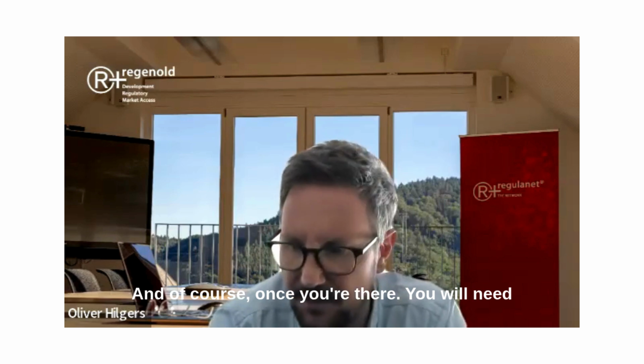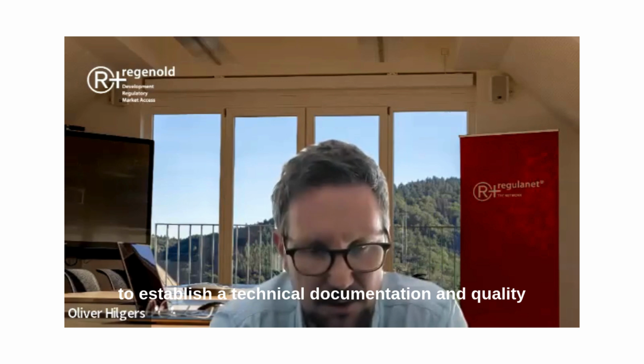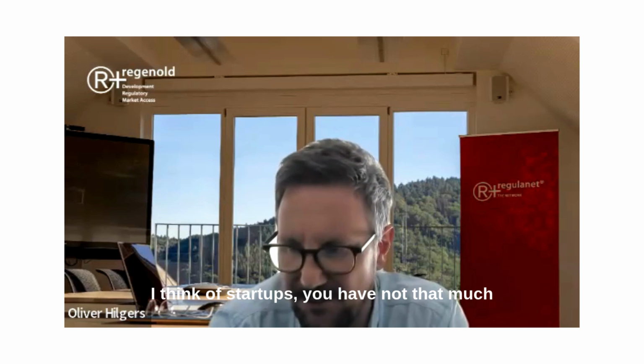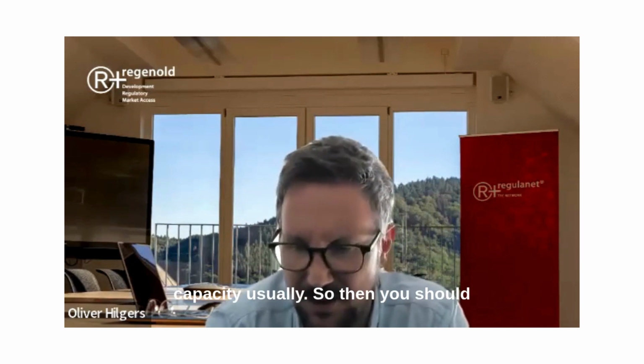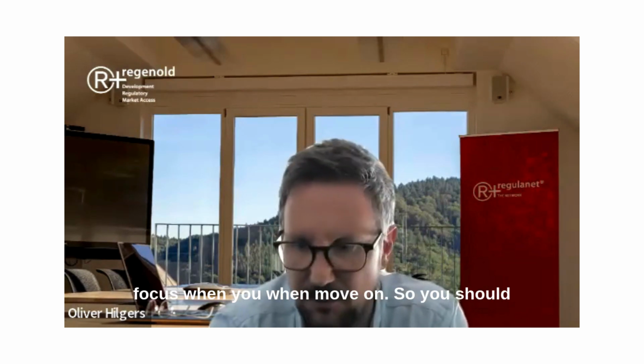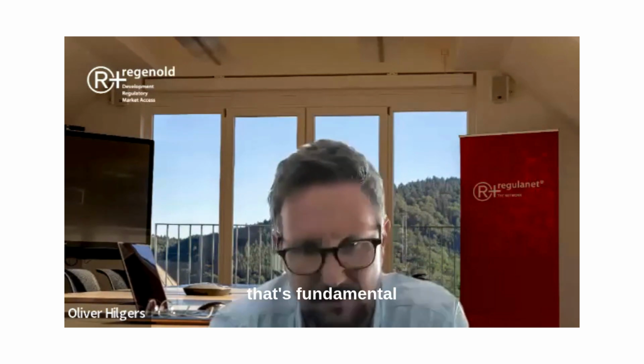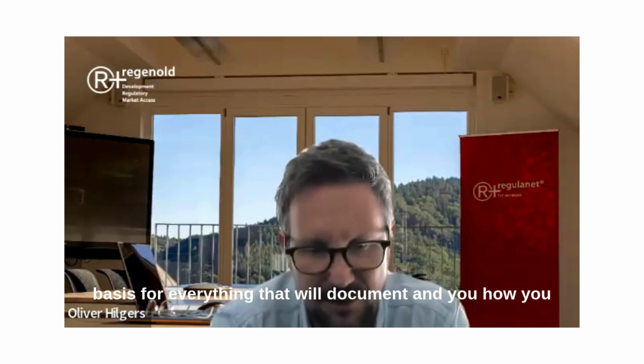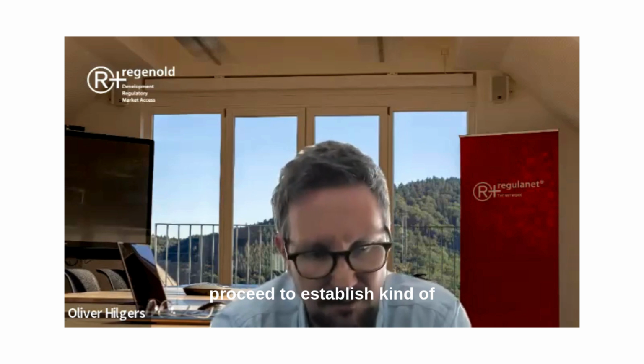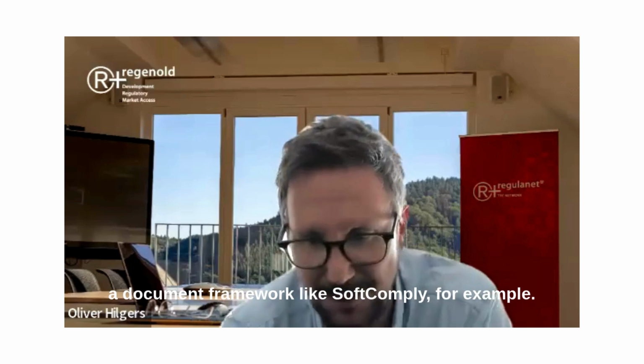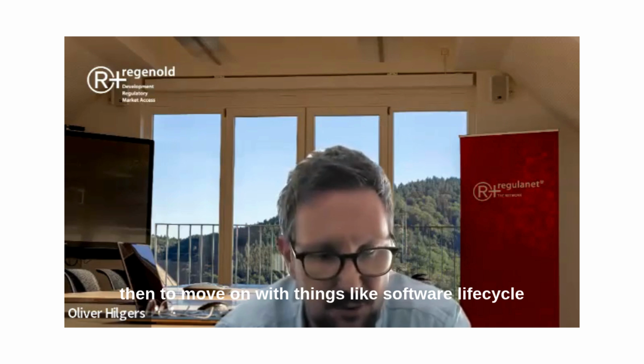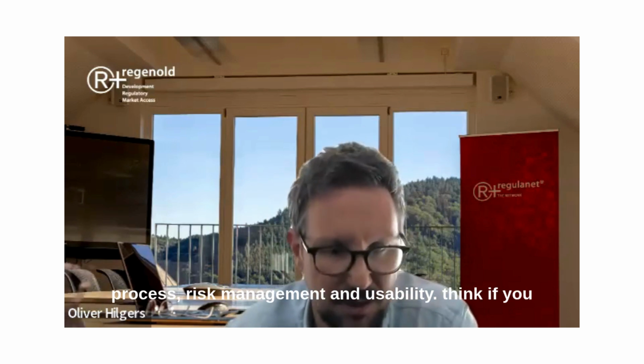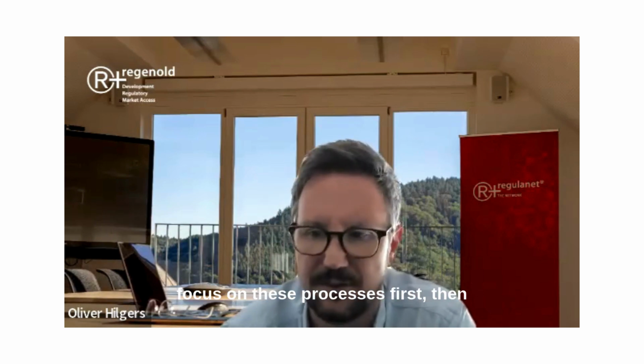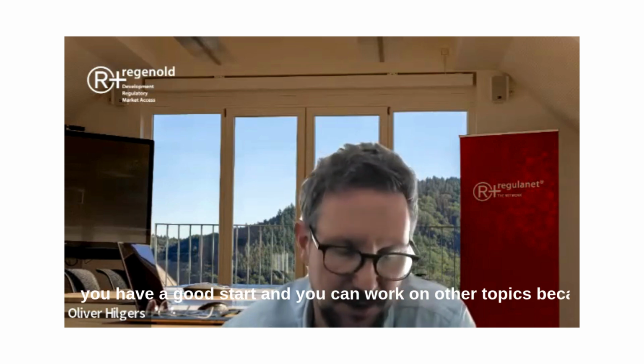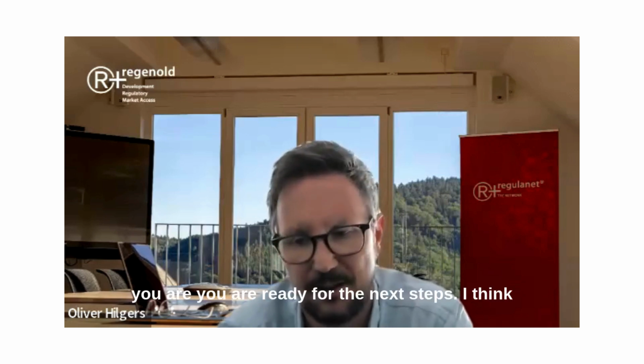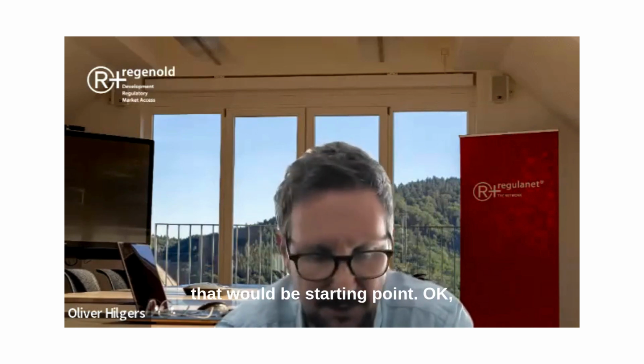And of course, once you're there, you will need to establish a technical documentation and a quality management system for your product. And when I think of startups, you usually do not have that much capacity. So you should focus when you move on. You should start with a document framework, because that's the fundamental basis for everything that you will document and how you proceed. Establish a document framework like SoftComply, for example. So you have to think about that in the beginning. And then move on with things like software lifecycle process, risk management, and usability. I think if you focus on these processes first, then you have a good start, and you can work on the other topics later. But if you have this core, you are ready for the next steps. I think that would be the starting point.